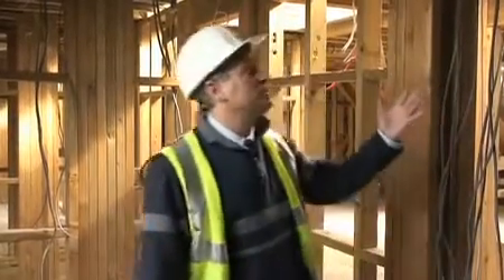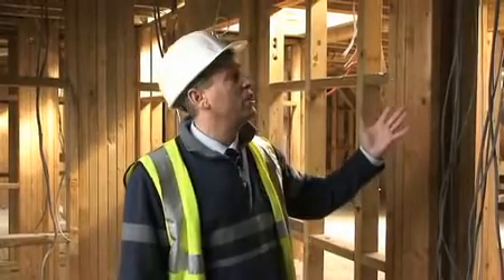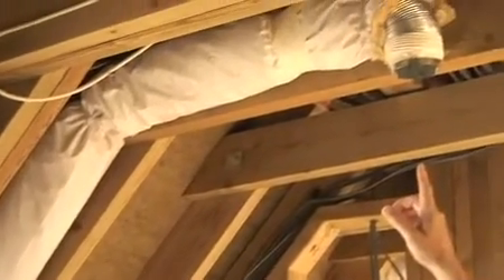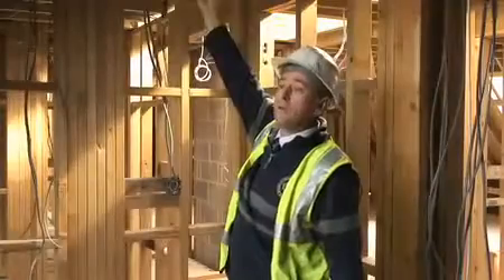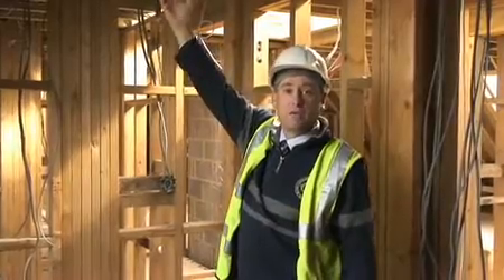Here we are now on the 2nd floor. We have no roof space in this particular building, so it does prove a challenge for the siting of the heat recovery ventilation unit and the running of the ductwork. So what we've done here is we've located the heat recovery unit at the end of the building within a plant room and run the ductwork in the backfill, where we have a small void, and then run the ductwork up between the rafters into the ceiling void and finished off here with a ceiling grill to provide fresh air, in this case, into the bedroom.